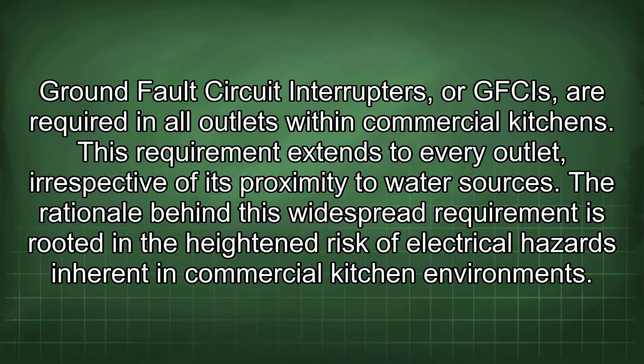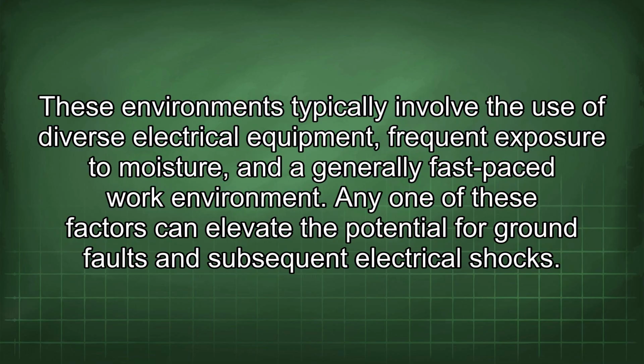Ground fault circuit interrupters, or GFCIs, are required in all outlets within commercial kitchens. This requirement extends to every outlet, irrespective of its proximity to water sources. The rationale behind this widespread requirement is rooted in the heightened risk of electrical hazards inherent in commercial kitchen environments. These environments typically involve the use of diverse electrical equipment, frequent exposure to moisture, and a generally fast-paced work environment. Any one of these factors can elevate the potential for ground faults and subsequent electrical shocks.